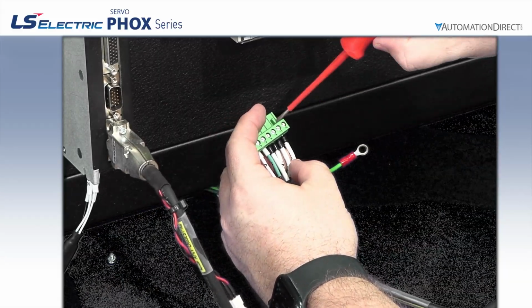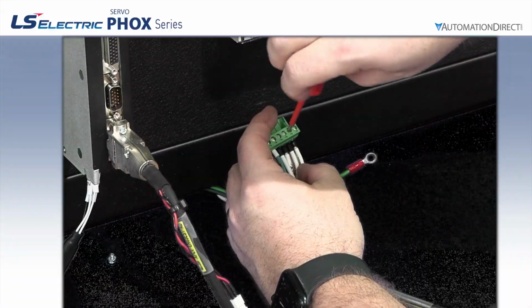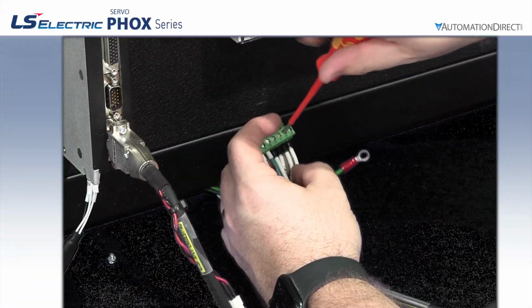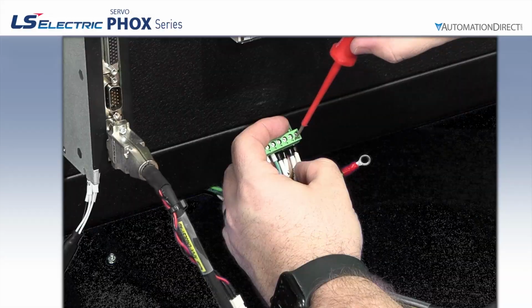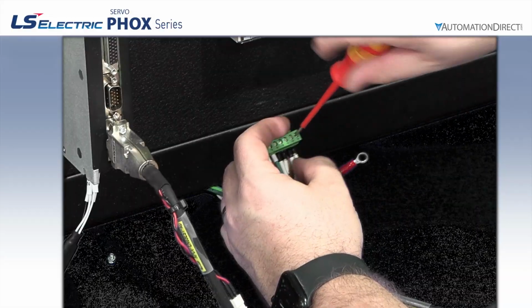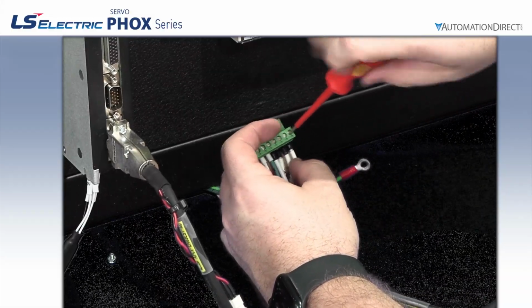Double-check polarity on all connections by referring to the drive label. In our example, we needed 24-volt power for the digital I/O functions anyways, and it's always a good idea to separate main drive power and control power whenever possible.